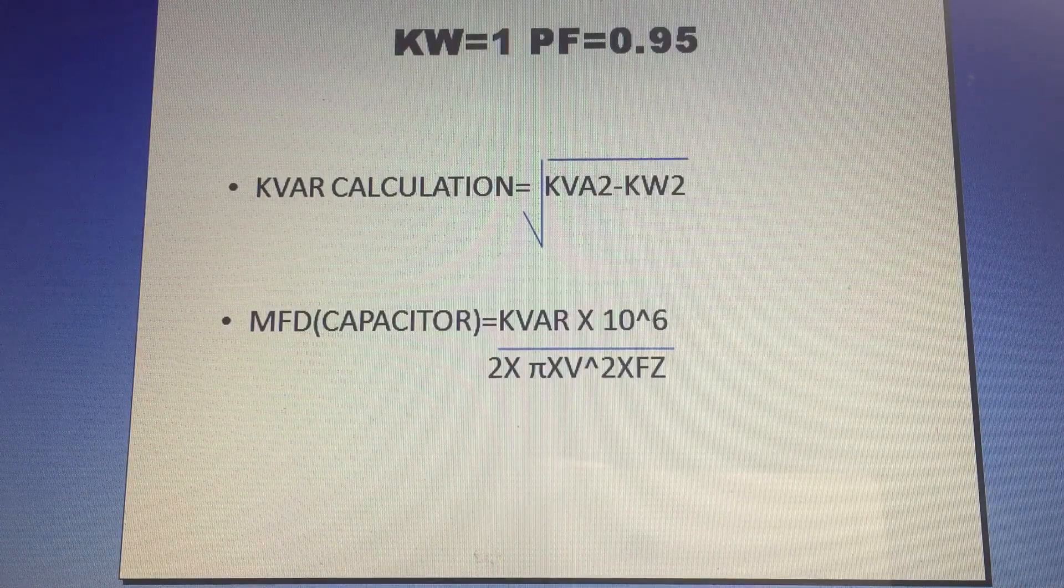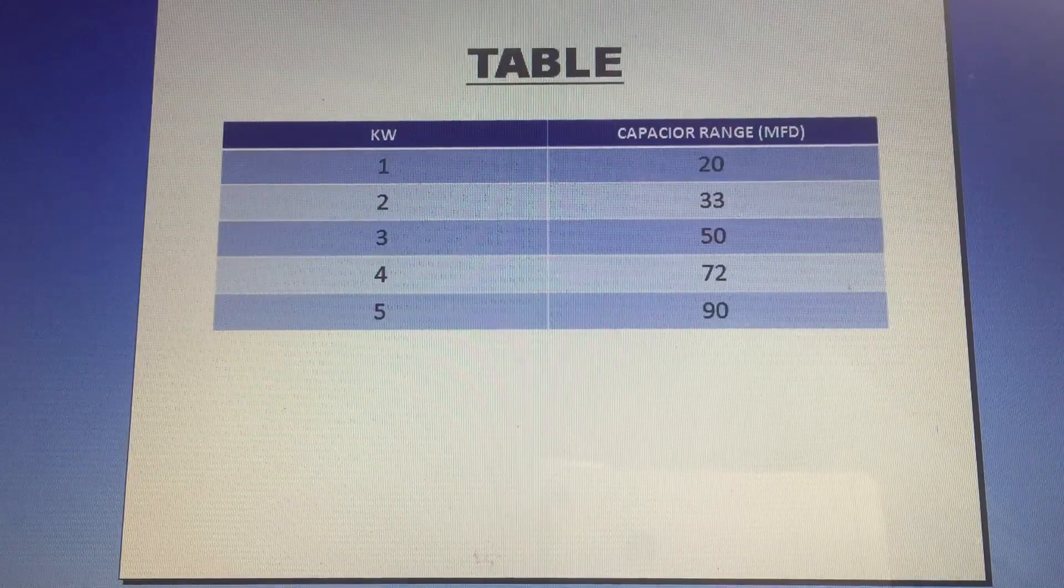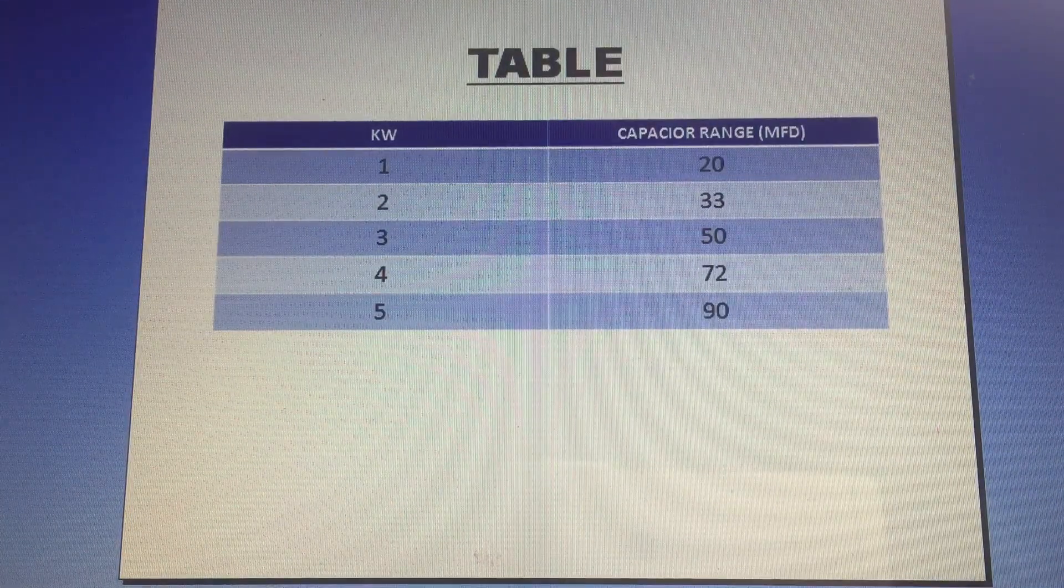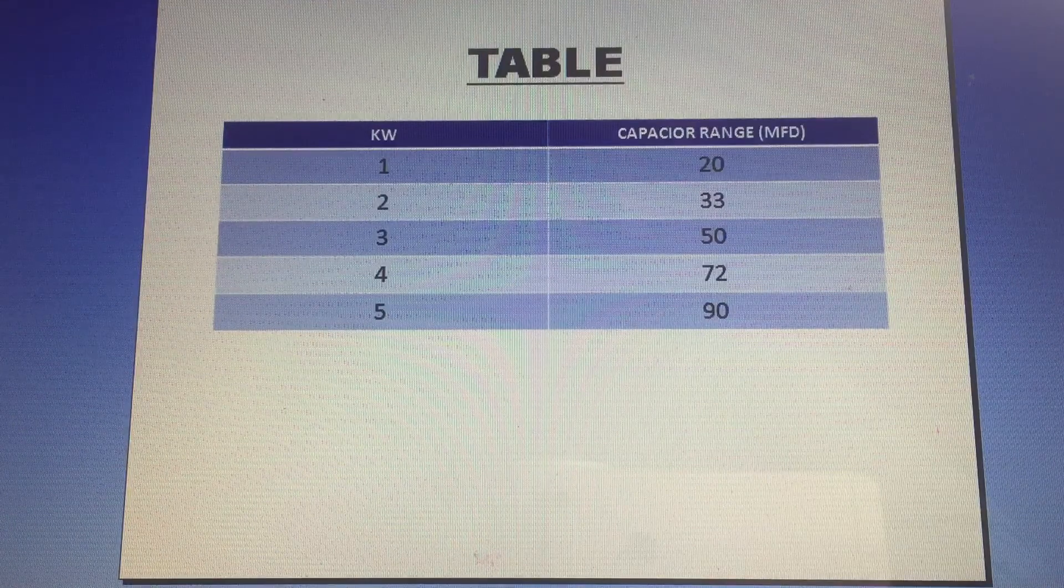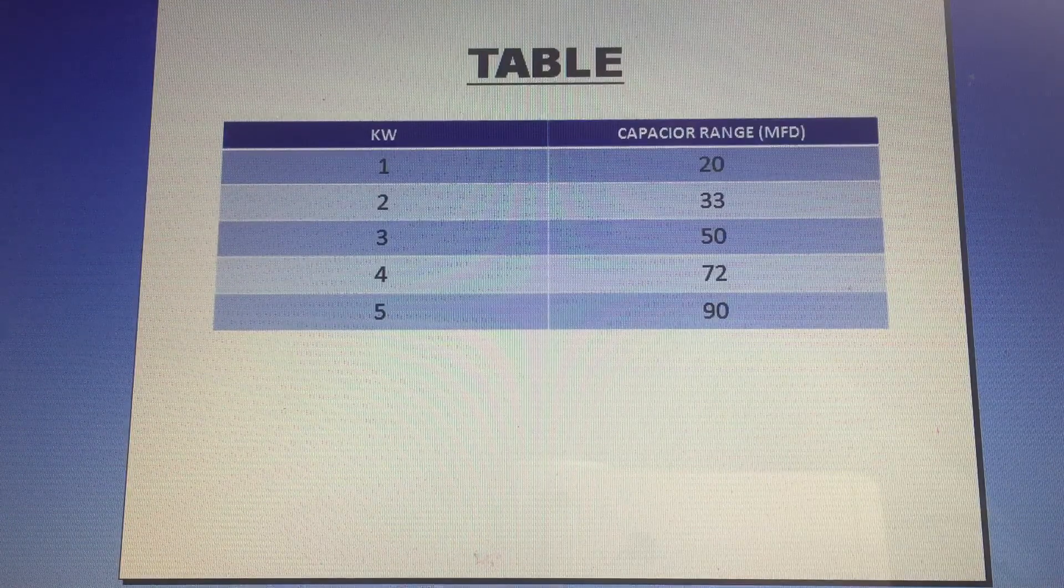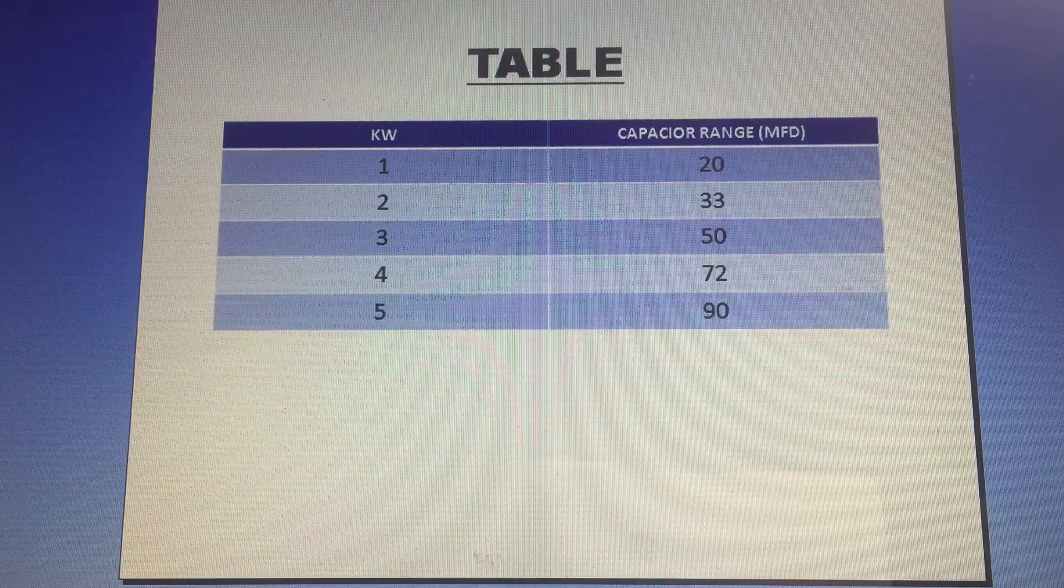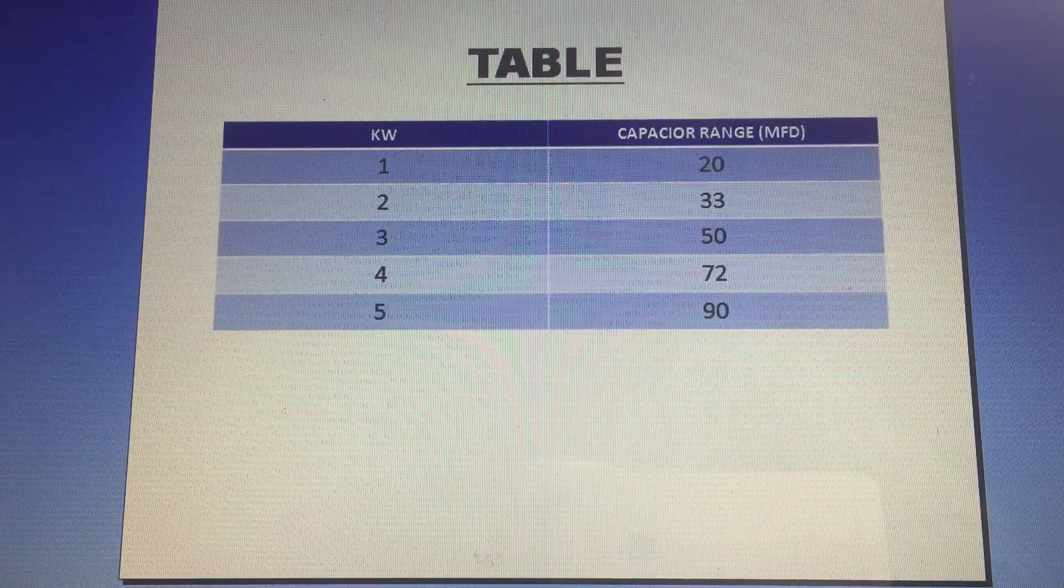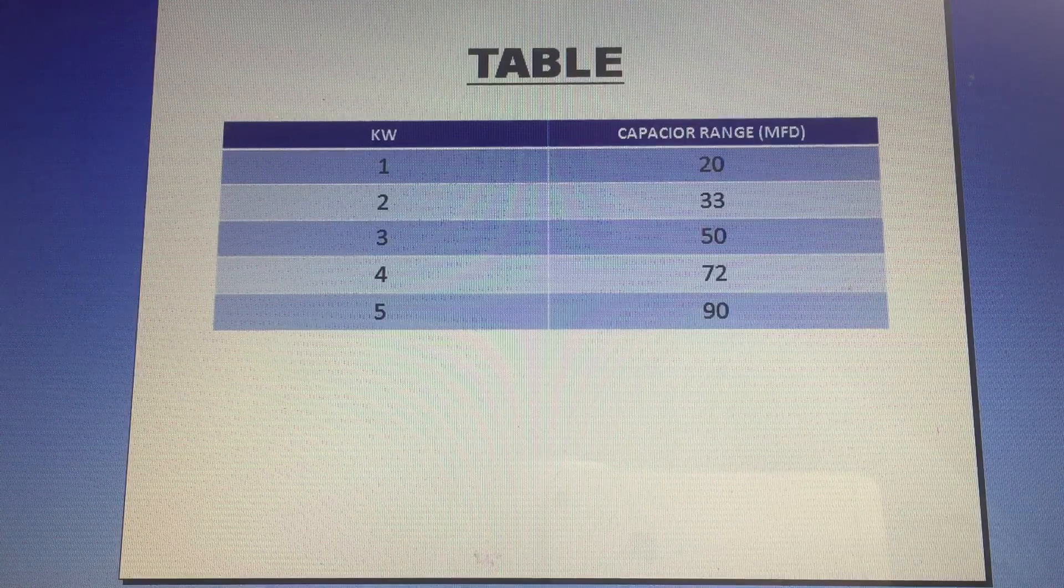If you do this, you get the capacitor value. I will show a table approximately. If you want to use 1 kW, use 20 MFD. 2 kW use 33 MFD, 3 kW use 50 MFD, 4 kW use 72 MFD, 5 kW use 90 MFD.